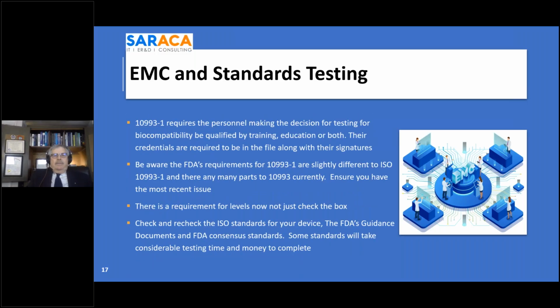10993 has changed recently, over the last several years. It used to be that you had in the guidance document a series of testing that was done, and all you do is check off the box and say that you did it. That's all changed now. It requires the personnel making the decision for testing for biocompatibility to be qualified by training, education, or both. Their credentials are required to be in the 10993 file, along with the signatures. Be aware that the FDA requirements at this time are slightly different than the ISO requirements.